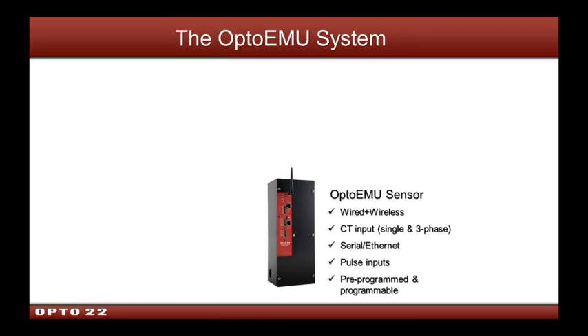If you had several of these devices distributed throughout a plant, the inputs to the device—if you were to connect directly to power wires, we accept CT inputs, current transformers. We can do either one 3-phase input or 3 single-phase inputs. We can also talk serial or Ethernet from this device, like our standard product, in the event we wanted to share data with a BAS system, a sub-meter, or a power quality analyzer. We also accept pulse inputs. Many of the smart meters that utilities have installed or are going to install into commercial and industrial buildings have a pulse output representing kilowatt hours, so we can accept those as well.